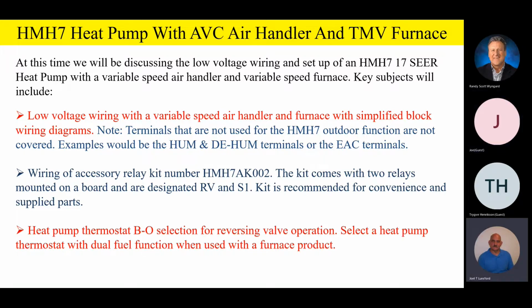Some examples would be like the HUM terminal. The HUM and DE-HUM terminals or the EAC terminals on the air handler or furnace are going to be strictly for indoor use, as far as dehumidification or electronic air cleaner and so on. Now, it should be noted also, please, that the wiring accessory relay kit number 002 will be required for the variable speed product.